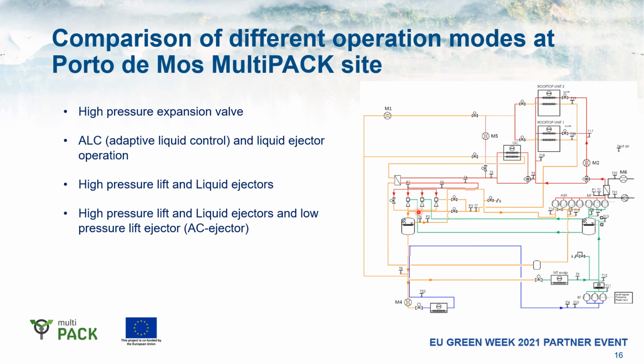The third set of measurements was containing the operation of both ALC, the liquid ejector, and the high pressure lift ejector. So here the high pressure lift ejector is recompressing gas from the suction gas accumulator to the receiver pressure level. And the fourth operation mode is, so to say, all the ejectors are on. So the liquid ejector, the high pressure lift ejector, and the low pressure lift ejector in operation, while the job of the low pressure lift ejector is to circulate liquid from the air handling unit and compressing it up to the receiver pressure.